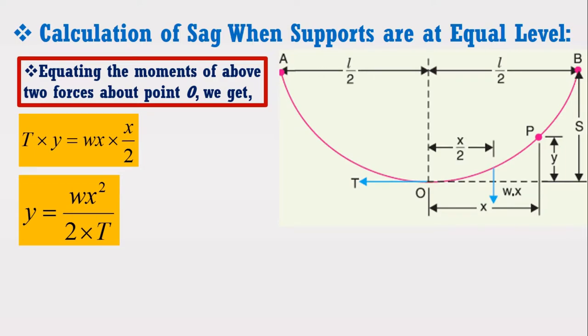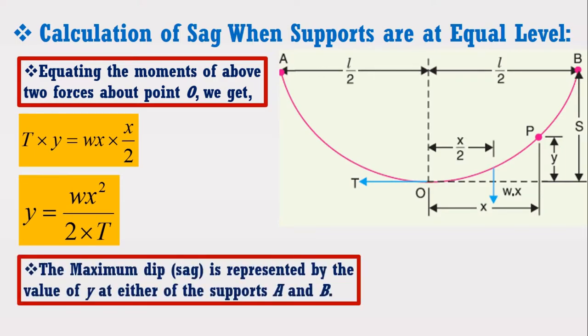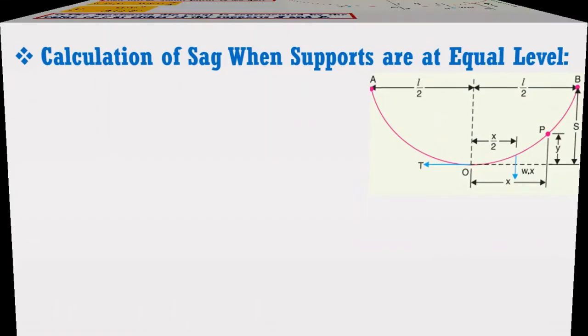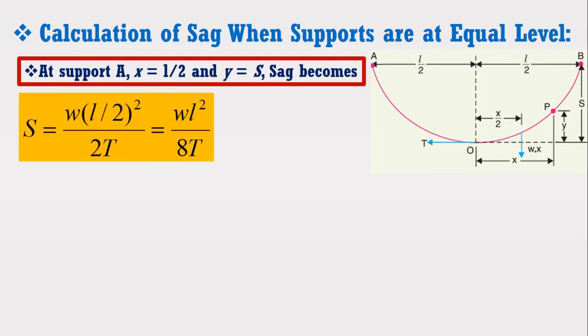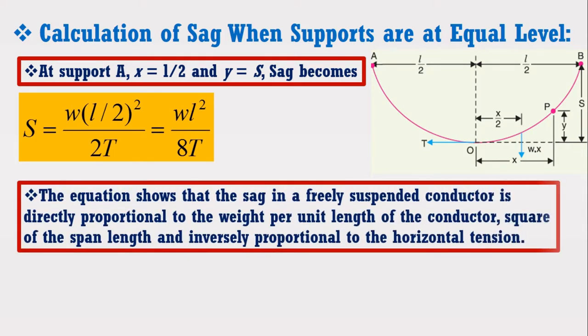The maximum dip or sag is represented by the value of Y at either of the supports A or B. At support A, X is equal to L upon 2 and Y is equal to S. Therefore, sag S becomes: S is equal to WL squared upon 8T. This equation shows that sag is directly proportional to the weight per unit length of the conductor and the square of the span length, and inversely proportional to the horizontal tension.